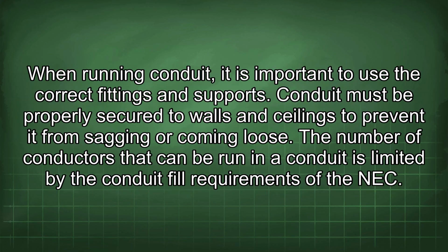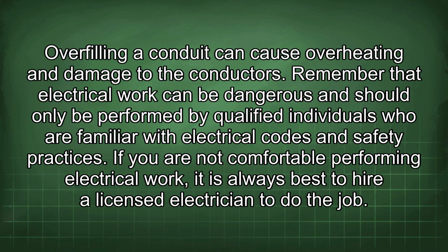When running conduit, it is important to use the correct fittings and supports. Conduit must be properly secured to walls and ceilings to prevent it from sagging or coming loose. The number of conductors that can be run in a conduit is limited by the conduit fill requirements of the NEC. Overfilling a conduit can cause overheating and damage to the conductors.